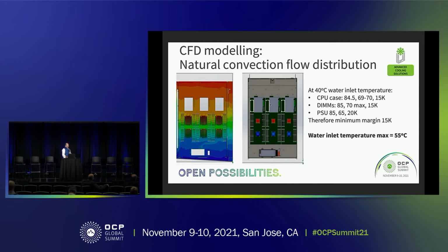On the right-hand side, we can see the temperatures of the case of the processors, and they are currently with a flow water temperature of 40 degrees. We find we have a 15-degree margin, so 15 degrees overcooling of the CPUs, which implies that we could operate this at a water inlet temperature of 55 degrees. So which is a great outcome from the simulation for warm water cooling for heat reuse.